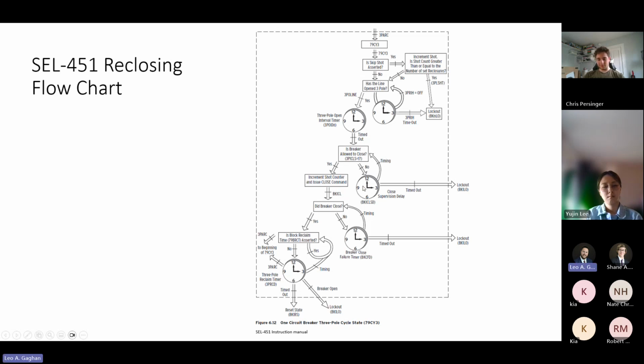So here's a pretty good flow chart from one of the SEL 451 manuals. You guys have got a 451 in the lab. I don't think we've got a lot of slides to go over, but this would maybe be the best use of our time. This is pretty much the flow chart in the relay and how it makes the decision to move to the next step in its reclosing cycle. If you are going to develop relay settings for an auto reclosing scheme, this is something that would be pretty valuable to work through.